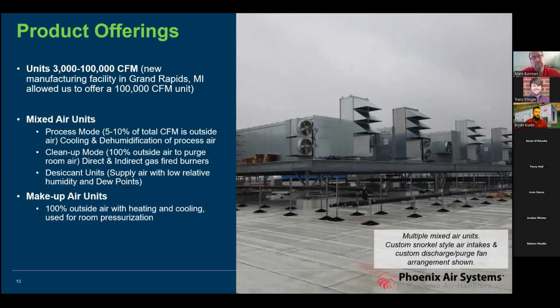One thing I want to add, Mark, just while we're on this picture, Mark mentioned these are pretty custom. Just examples of that. You can see the custom snorkel hoods installed on these units shown. You can also see the integrated exhaust fans are turned at a 90-degree angle because the units are in parallel. Obviously, we don't want to be blowing moist sanitation air directly into the intake hood of the unit that's next door. So again, just a good example of these are custom and are designed to be fit in your unique applications.